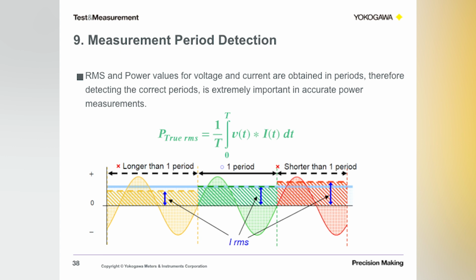Let's take a look here at an example of a clean waveform, a current waveform that I have here. Now, if you use the measurement periods denoted by the yellow and the red portion of the waveform, you can see that the RMS values that are calculated will either be lower or above the expected solid blue line, right? If you use the measurement period shown in the green region, then the RMS value is the same as what is expected, right? So you can see that if you don't use the correct measurement period, the measurement will not be correct. For accurate power measurements, not detecting that correct period of calculation will result in a significant error.